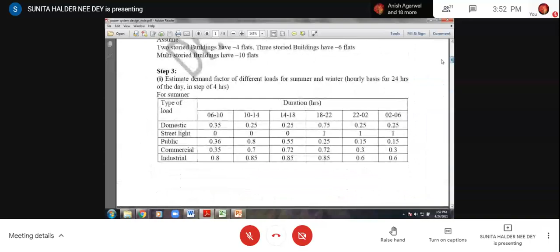When you calculate the load, we shall assume that there is a rated voltage. Then obviously when actual current flows, the current will be lesser. So load segment current we shall calculate in this way. We shall assume a flat power factor of 0.85, right? And here we are considering all powers as the connected load, not the actual load or the maximum load.